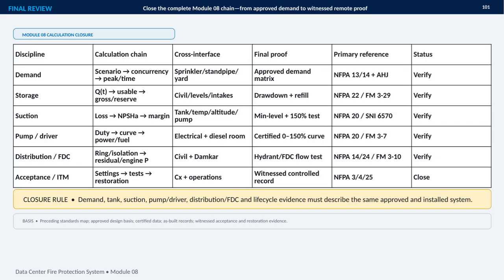This final review closes the complete Module 08 chain, from approved demand through witnessed remote proof. The key question is whether every calculation and record describes the same approved and installed fire protection system. The review begins with demand, scenario, concurrency, and peak duration linked across the sprinkler, standpipe, and yard systems. Storage then converts the required flow over time into usable volume, gross volume, reserve, drawdown, and refill evidence. Suction confirms that losses, tank conditions, temperature, altitude, and minimum water level still provide adequate NPSH margin. The pump and driver must connect duty, performance curve, power, and fuel to certified testing.